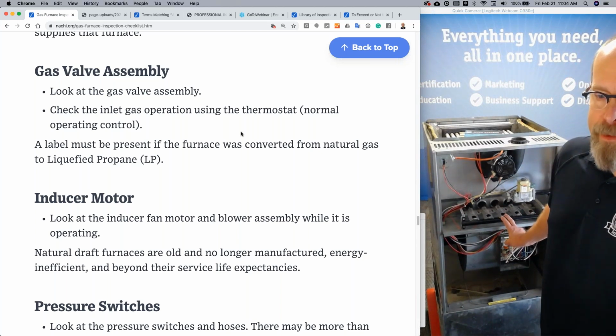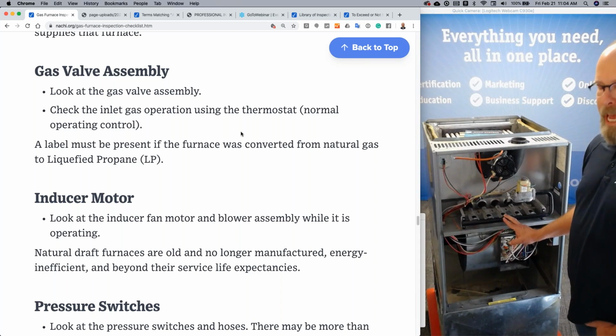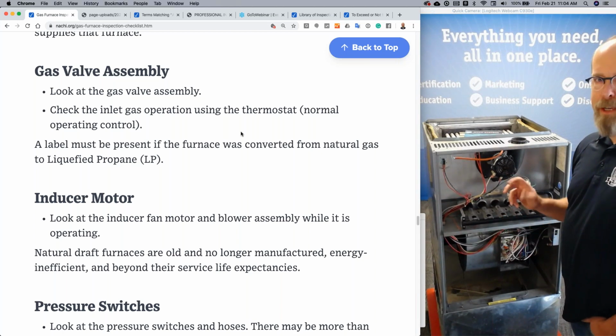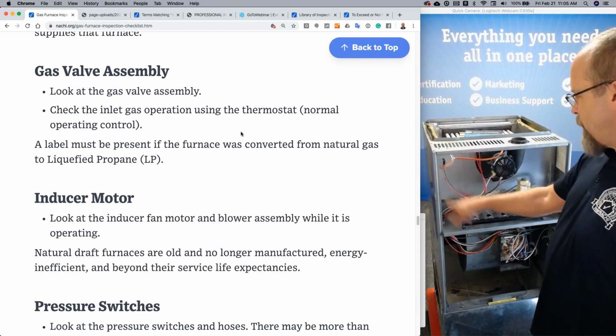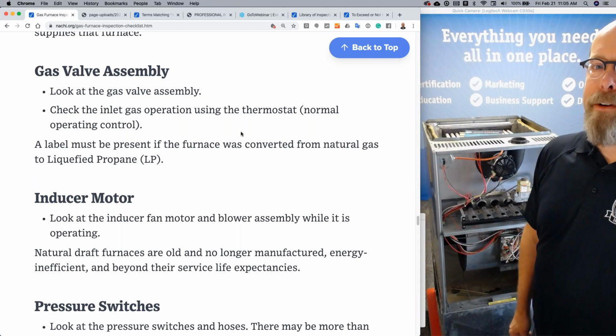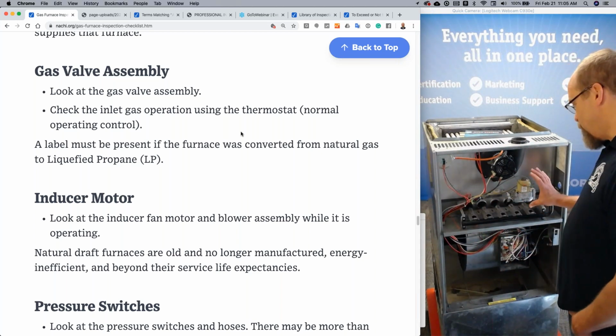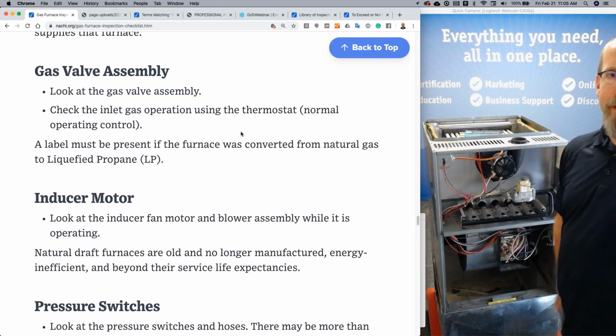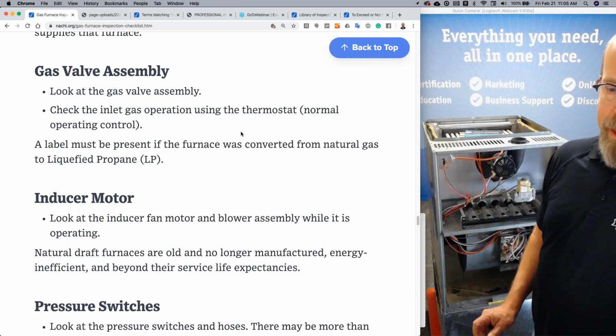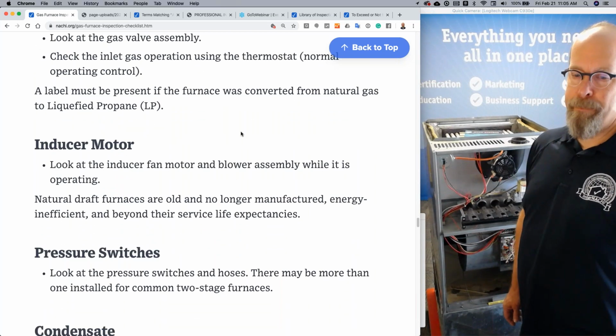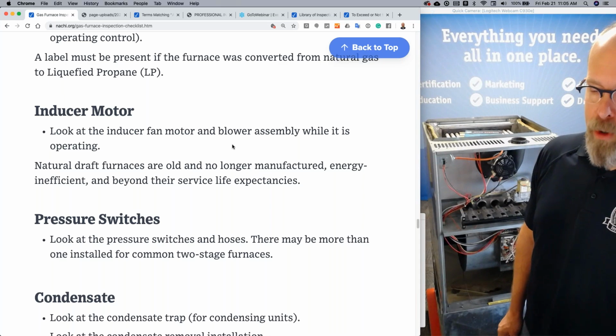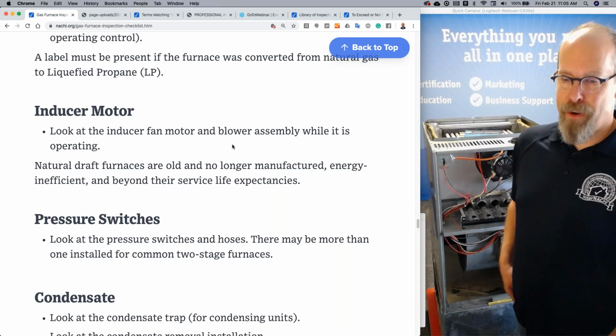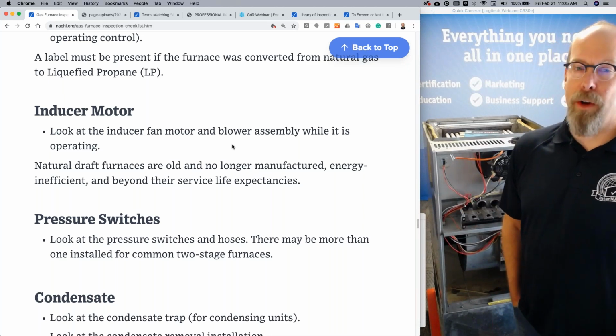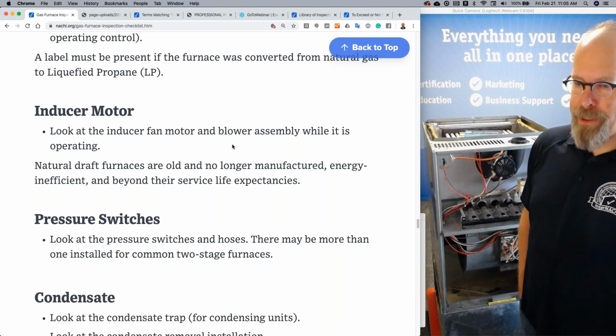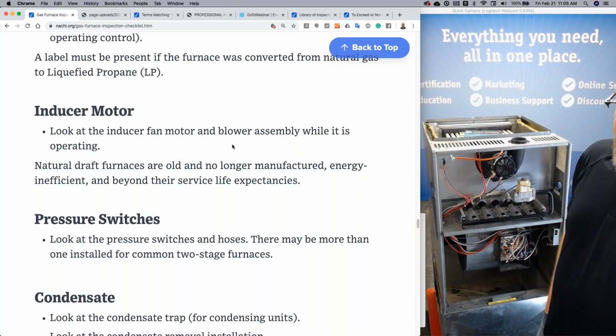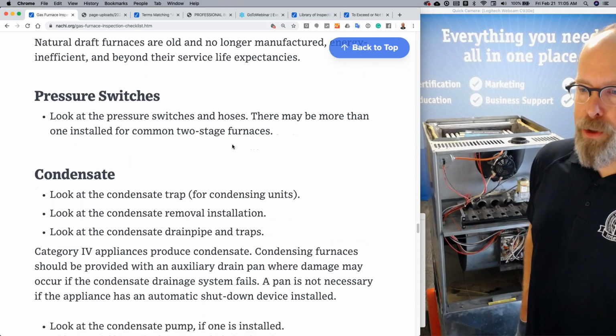Look at the gas valve assembly, check the inlet gas operation during the thermostat sequence. So turn the unit on, go upstairs, call for heat, come back down, and you'll hear it click, right? And then you'll see it'll open up, the gas will go through the manifold, and it will ignite. If it's converted to liquefied propane, there should be a label. Inducer motor. Look at the inducer fan motor and blower assembly while it's operating. Natural draft furnaces are old and no longer manufactured. That's category 1, inefficient, 60% efficiency furnaces. They're inefficient and beyond their service life expectancies. They're just no longer made.